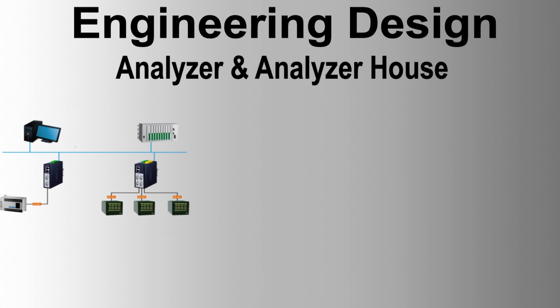Type of sensors. Select sensors appropriate for the types of gases present in the analyzer house. Common types include catalytic bead sensors for flammable gases and electrochemical sensors for toxic gases. Alarm systems. Gas detection systems should be connected to audible and visual alarms to alert personnel in case of a gas leak. These alarms should be loud and visible enough to be noticed throughout the analyzer house and any adjacent areas. In case of a significant gas leak, the gas detection system should be capable of triggering automatic shutoff valves to isolate the affected area and prevent further gas flow.